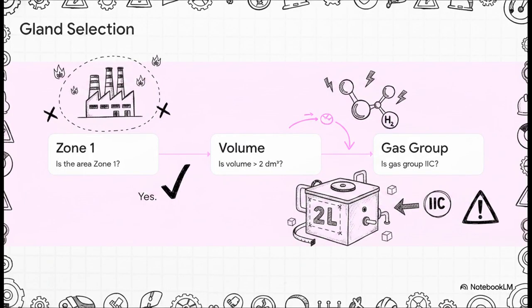Luckily, the IEC 60079-14 standard gives us a very specific gland selection flowchart to follow for this. First, you identify the zone, in this case, Zone 1. Second, you check the enclosure volume. Is it greater than 2 liters? And third, check the gas group. Is it IIC? Now, usually in Zone 1, you need a robust, certified compound-filled barrier gland, but there's an exception path. If the gas group is not IIC and the internal volume is smaller than 2 liters, you can actually use a standard elastomer compression gland instead.